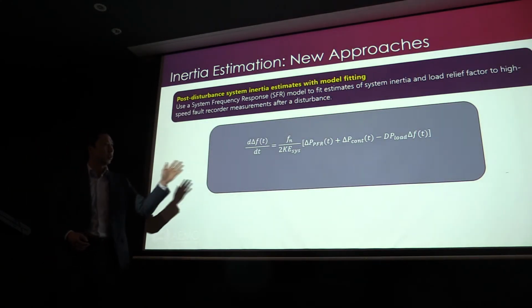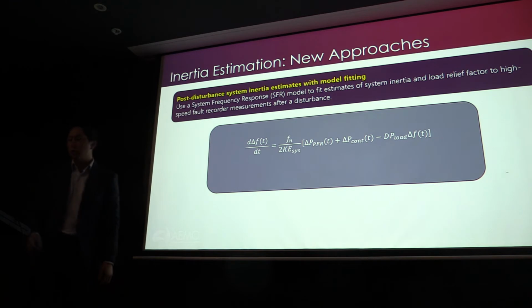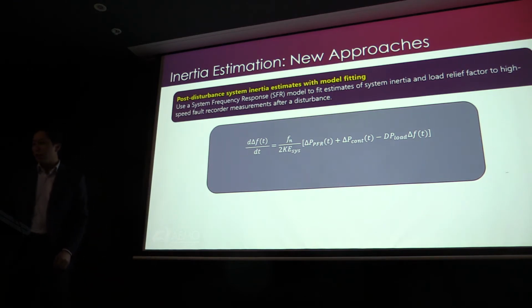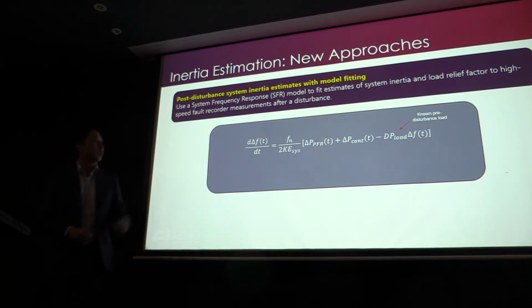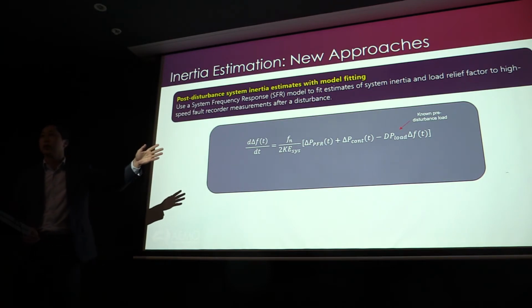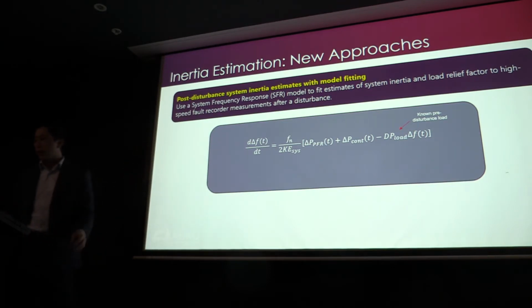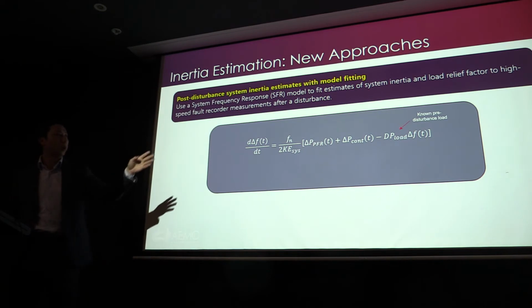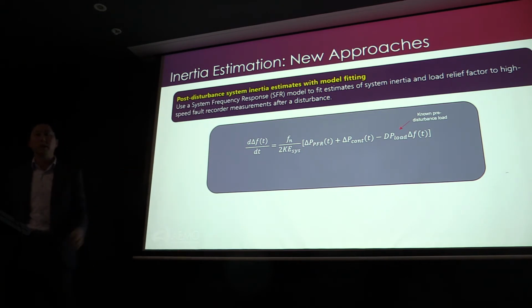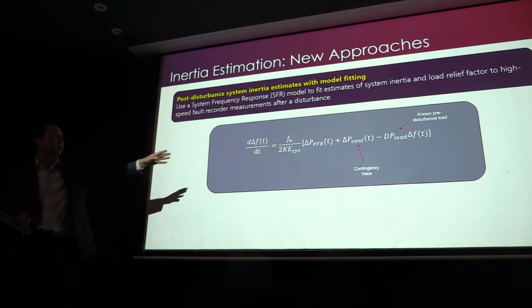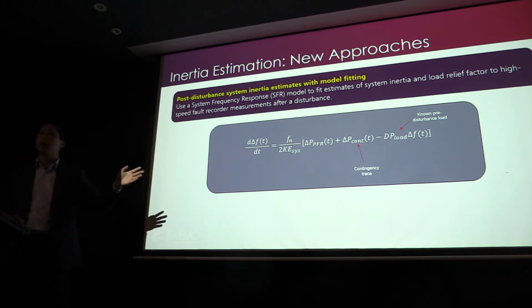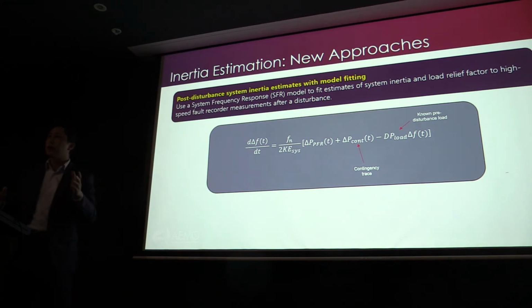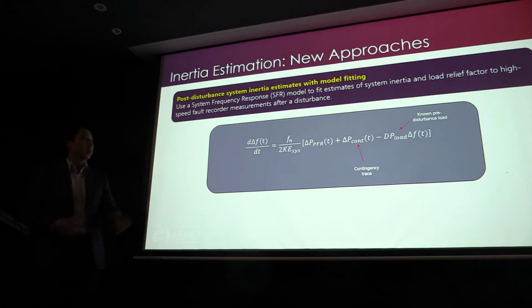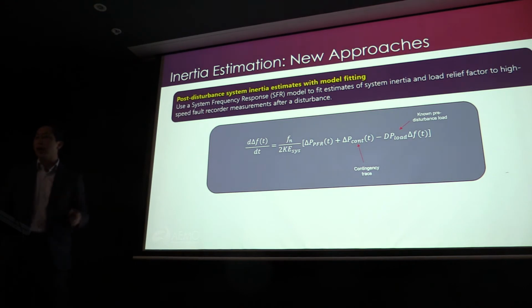This is the differential equation for the system frequency response model. I'll just talk through it so it's not so daunting. The first point to note is that we know what the load is there. That's the pre-disturbance load, so we know that, and we're trying to estimate D, which is the load damping or the load relief factor. So we actually have the contingency as a trace. So even if it were a ramp down, we can see it as a ramp down, and we can plug it in because we're now using more of the data rather than just a simplified swing equation.